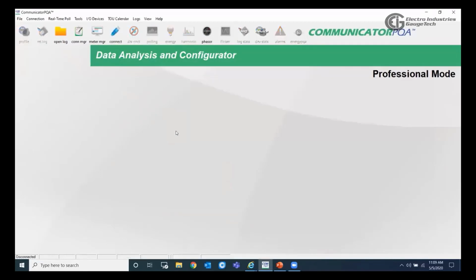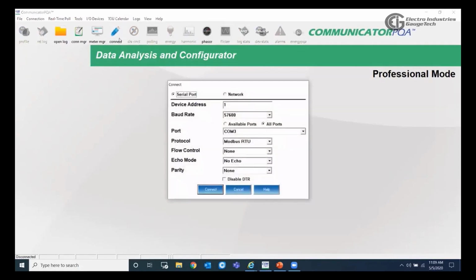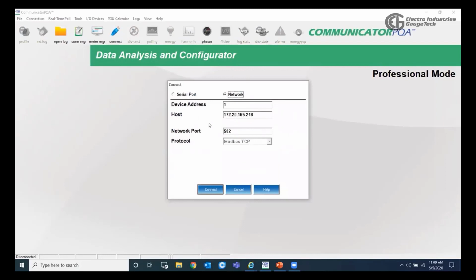and disconnect to show you how we can connect using the Ethernet port or the network port. So I will hit connect and choose network. From here, we have the device address, which is also by default 1. And the host would be the device or the meter's IP address. The default IP addresses for our meters would be either 10.0.0.1 or 10.0.0.2, depending on the model. But my meter now has an IP address 10.0.0.14. The network port by default is 502. And the protocol, of course, for the network should be Modbus TCP.